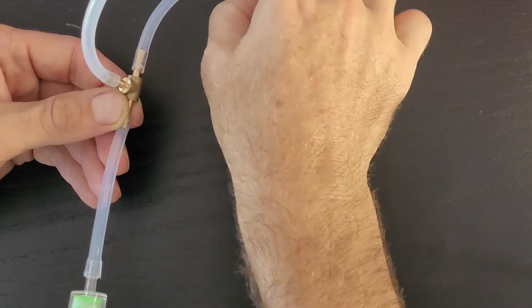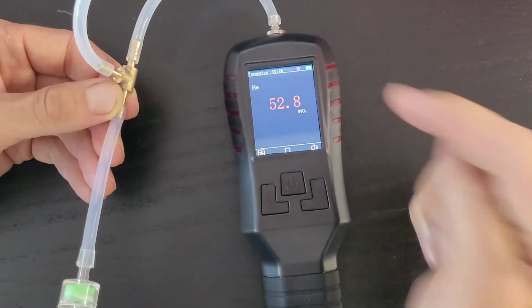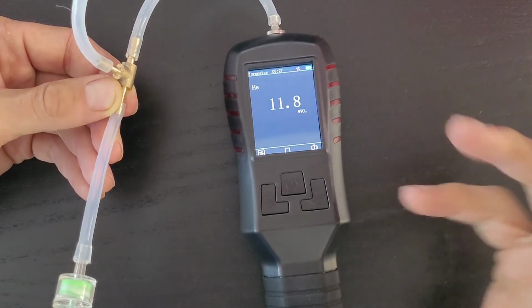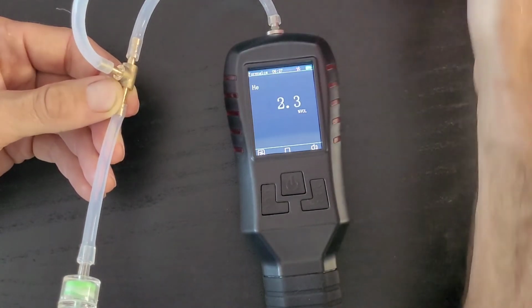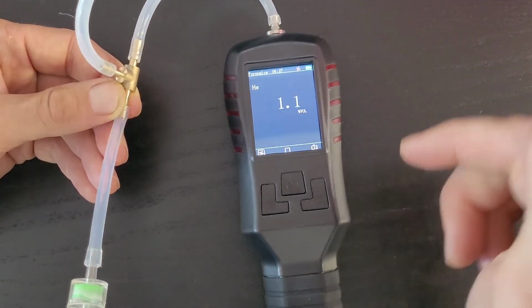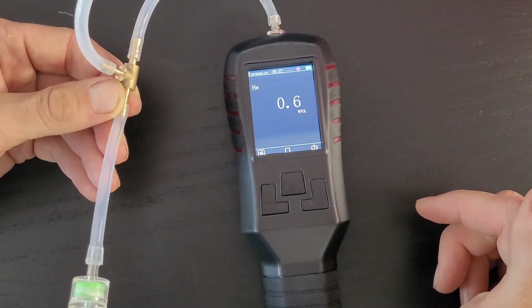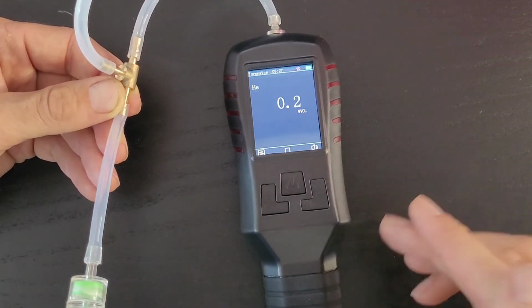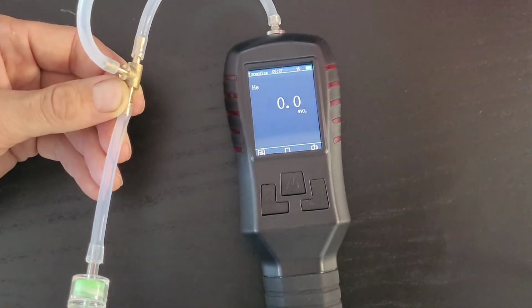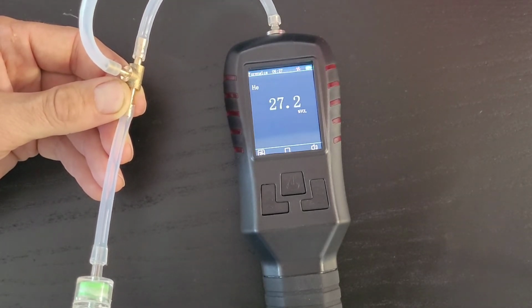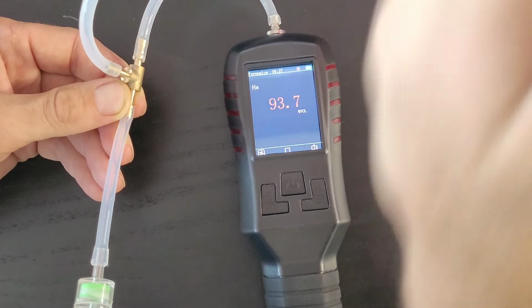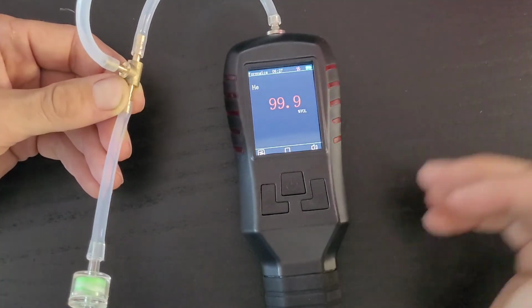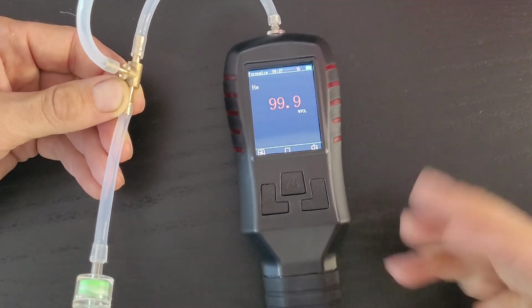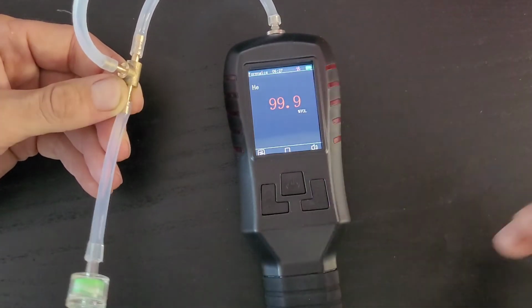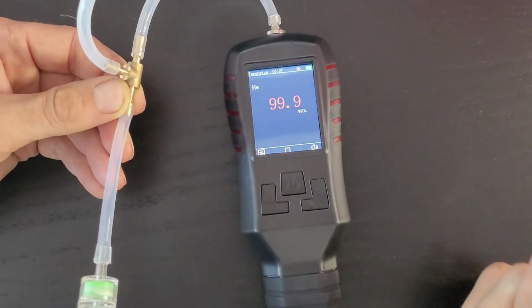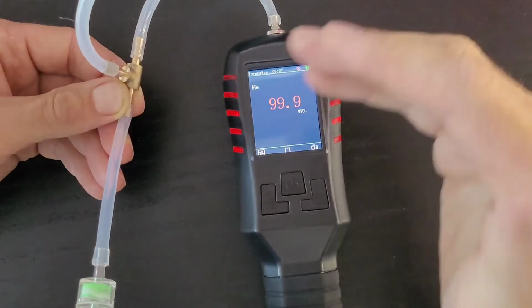Turn off the helium. Make sure it goes to zero. This is what I personally like to do. Get some verification going, okay? If you're happy with it going to zero, you just want to check that it's gone to zero. I'm going to reapply my helium, okay, to make sure that it's actually going to go back to where I calibrated it, that 99.9, bang, exactly at 99.9. And I have confidence now that this guy is zero calibrated and it is span calibrated. Pretty simple as that, folks.